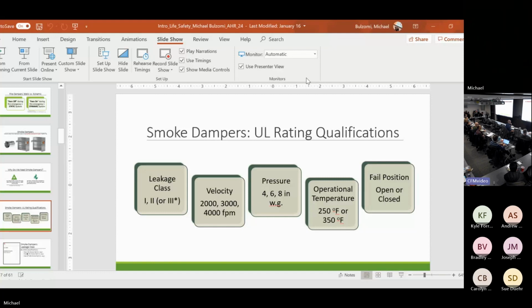It rarely ever happens. And the biggest problem you're going to have is the label on the damper is wrong. You cannot relabel it. I cannot, you cannot, nobody can relabel a damper in the field except for UL. You'd have to call UL, pay them to do a field inspection, and then come out and relabel the damper. The point is, if you're doing smoke control or you have the need for fail open smoke dampers, label it on the drawing somewhere. We're going to always assume it's fail closed. Every damper we sell, we're going to assume fail closed. It's an industry standard. The fail open, again, is only used for smoke control. You can have a fail open fire smoke damper as well, and those are very special applications.